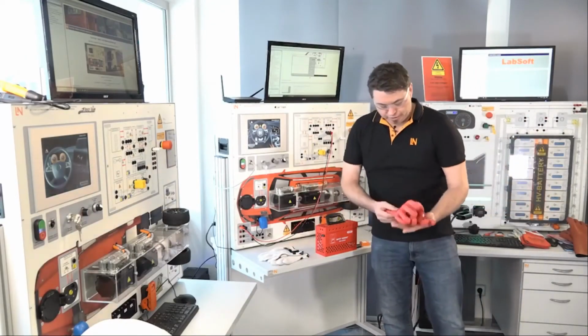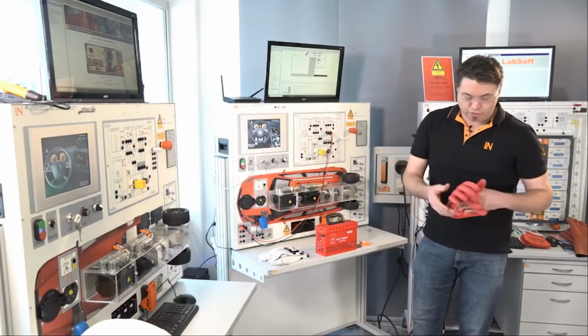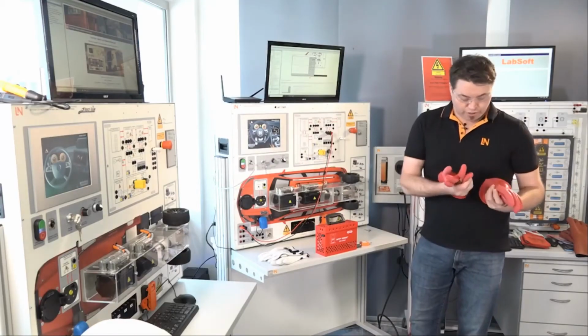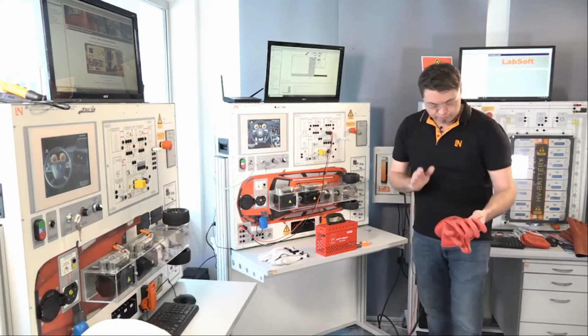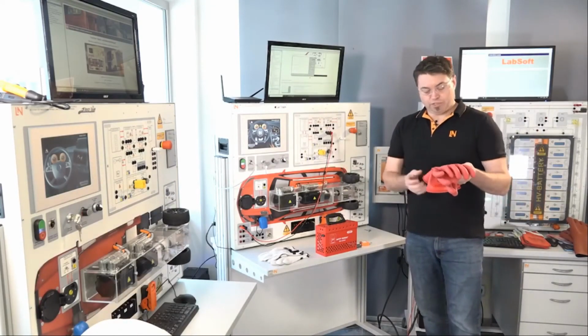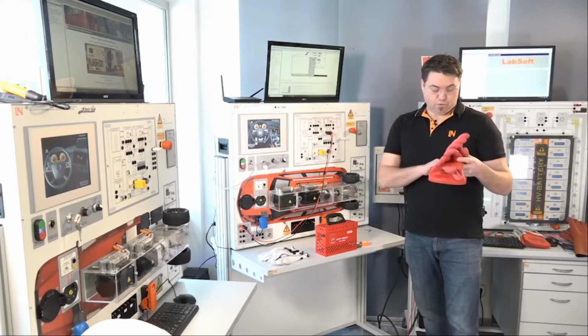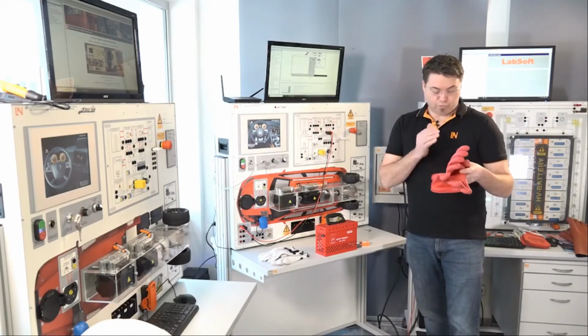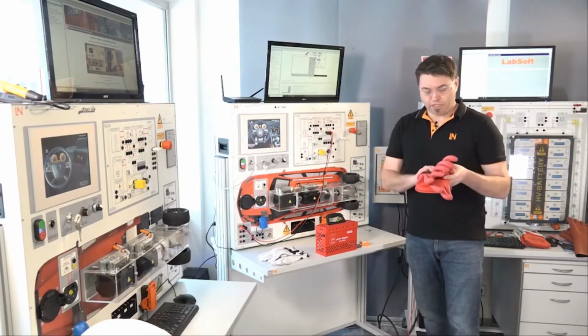There's a number of things we need to test first with our gloves: make sure they're in good condition, which these ones look like they are. We also need to make sure the date is within date - when was the last time they were tested - and we fall within 6 months, so these are okay to use.